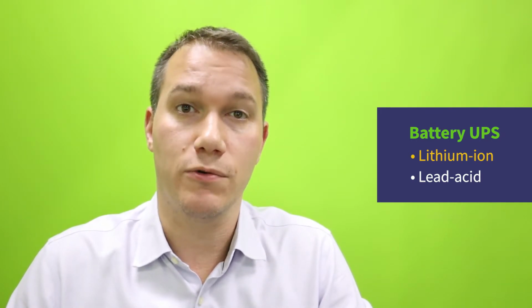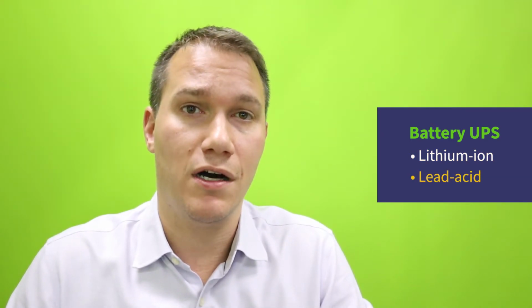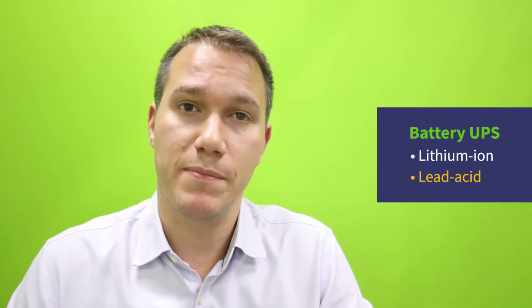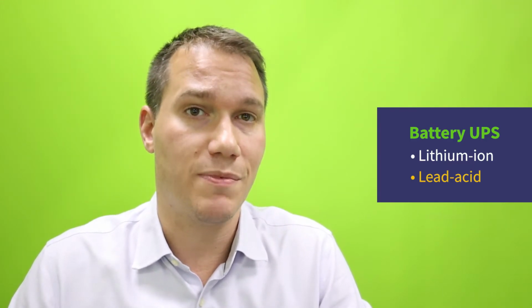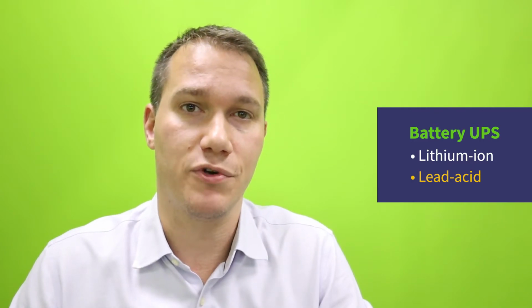The third type of technology data centers use are battery UPSs. These can be subdivided into two groups: lithium-ion batteries and lead-acid batteries. Lithium-ion batteries are the kinds you find inside your smartphone, and they're typically between 50 and 80% smaller than lead-acid batteries. They can also be power cycled quite a few more times - in fact, lithium-ion batteries can be discharged and recharged up to 1,000 times versus 200 to 400 times for lead-acid batteries. Lead-acid batteries, by comparison, have been around for quite a bit longer, so their reliability record is a bit better. But perhaps most importantly, lead-acid batteries are quite a lot cheaper than lithium batteries, which is why they're still the preferred battery of choice for most data centers.